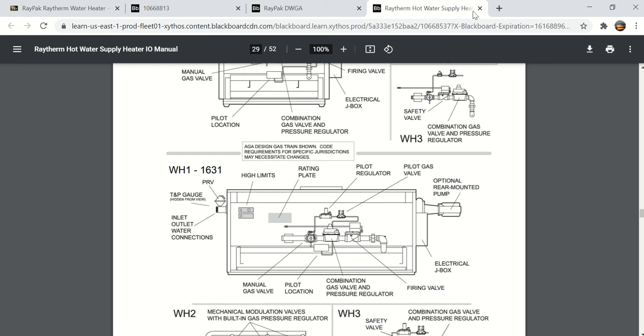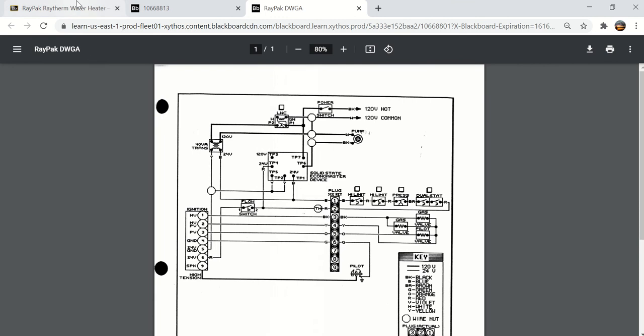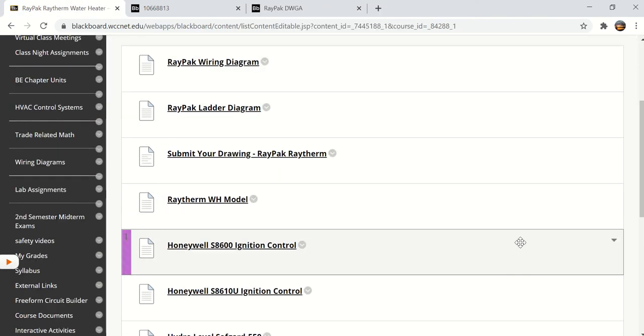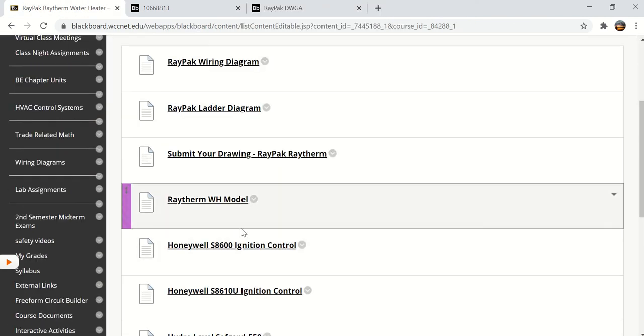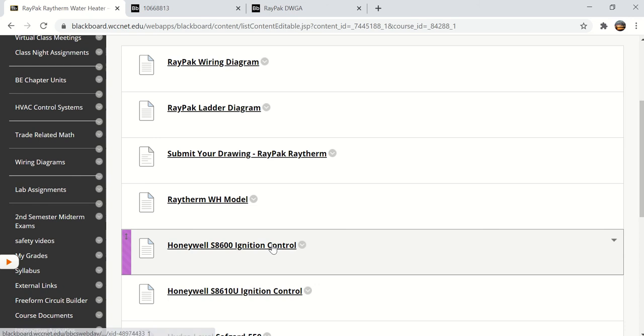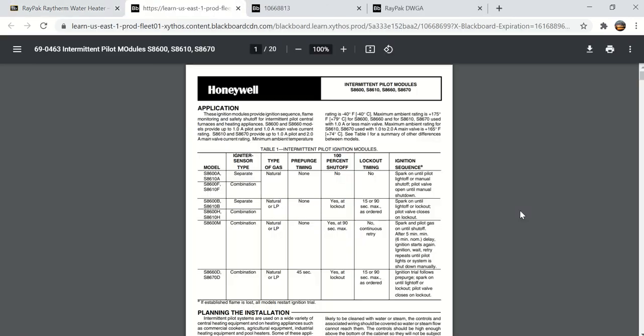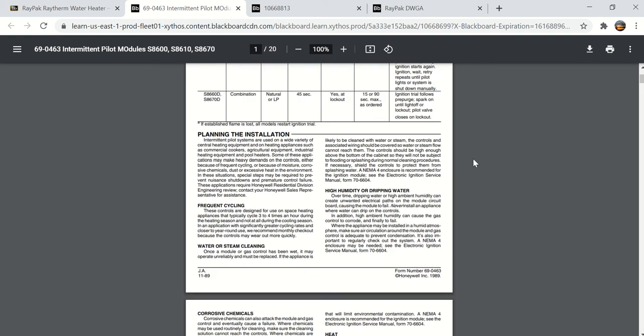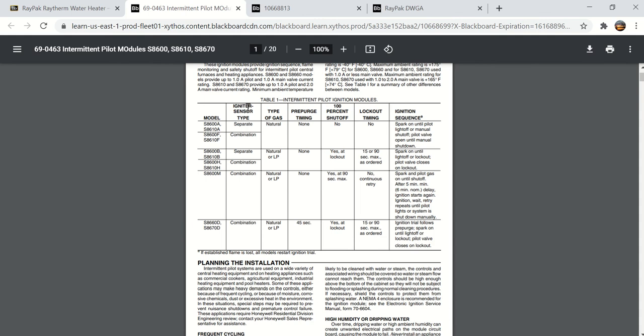So, close that and go back. And one other thing I put on here, here's the two types of ignition, Honeywell ignition control documents. This one is for the S8600 or the S8610. You see here that when it says igniter versus sensor, igniter sensor type, some of them can be separated where you have a separate igniter, separate sensor. Some of them are combination, like the one we're talking about is a combination.